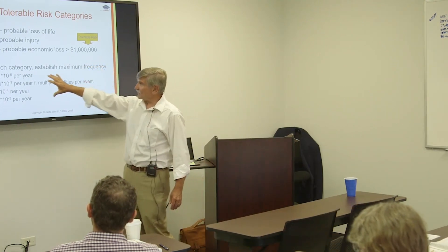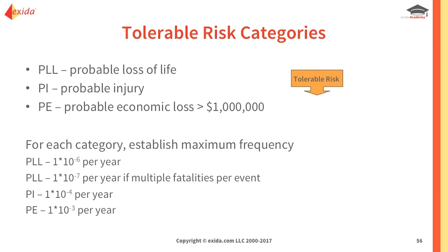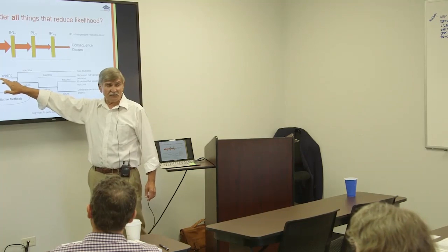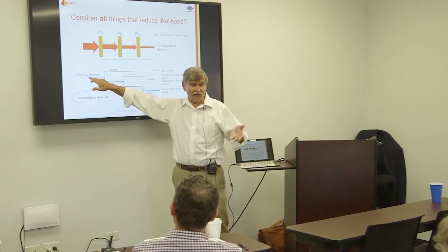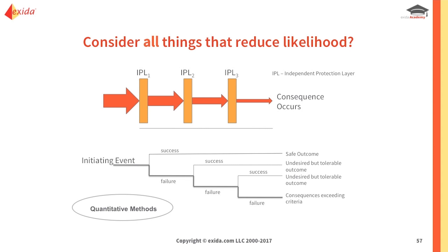Metrics used are probable loss of life, probable injury, probable economic loss greater than a million, or whatever the tolerable risk criteria is. For each category you establish a maximum frequency — a common method. Sometimes if multiple fatalities can occur, the frequency is lowered. You get the frequency of the initiating event, then for each protection layer ask: will it work or will it fail? If they all fail, we get consequences exceeding the criteria. The safe outcome is when one of the layers works.